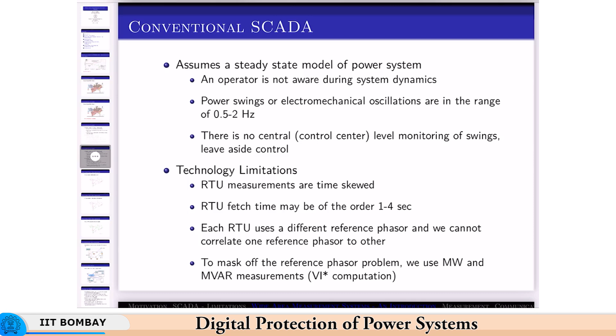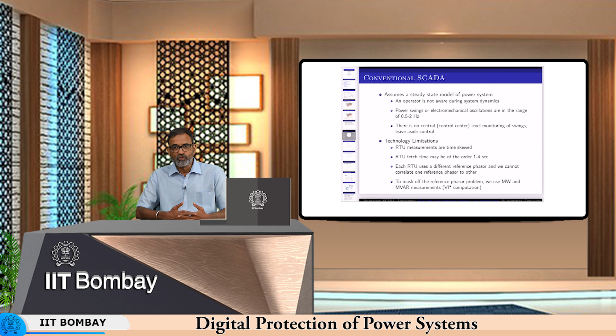To mask this, traditional SCADA used voltage magnitude, P and Q, that is VI star. P means megawatt and Q means MVAR. We use only the voltage magnitude, not the voltage phasor with angle, just the magnitude. That is why you got a non-linear state estimator with convergence problems, since you have to have an iterative solution. All these problems result from lack of a common reference phasor and use of local references.